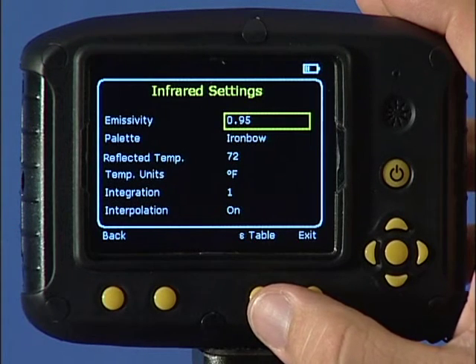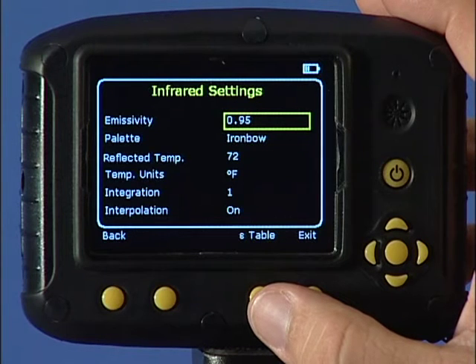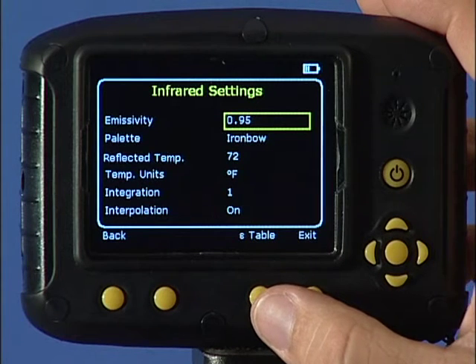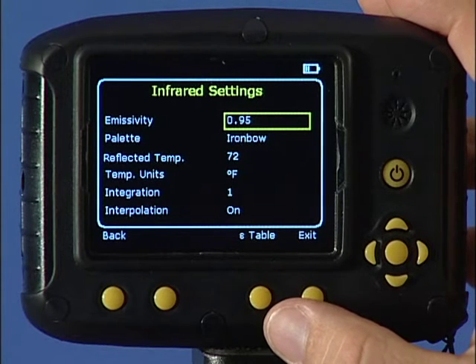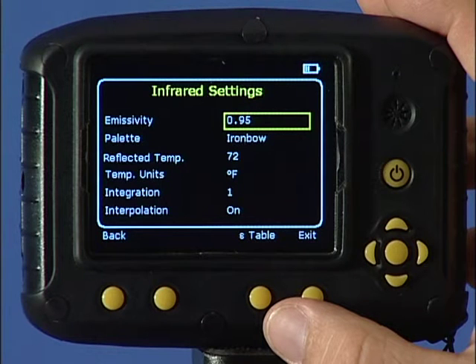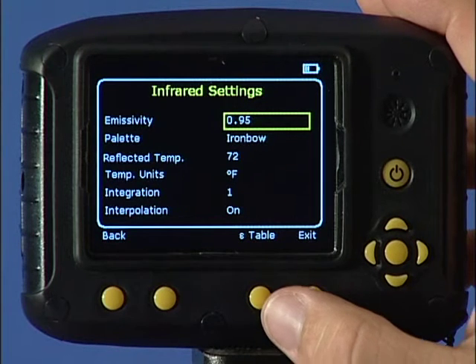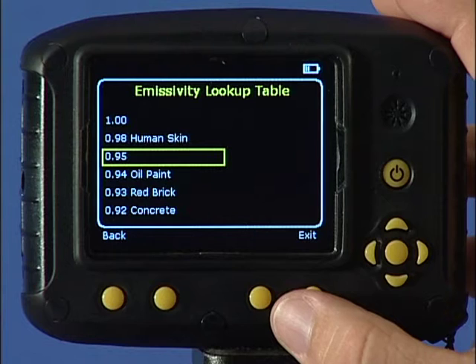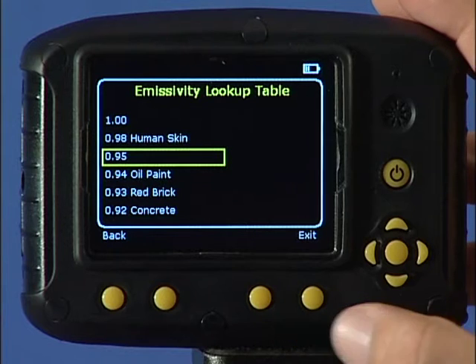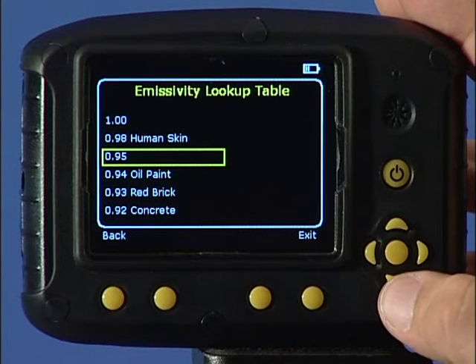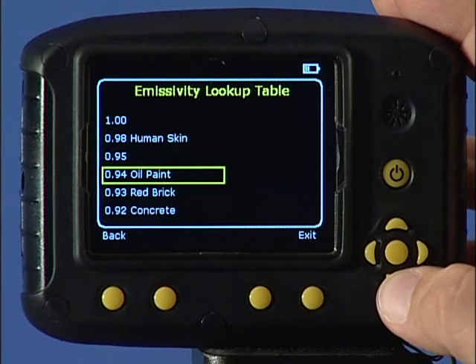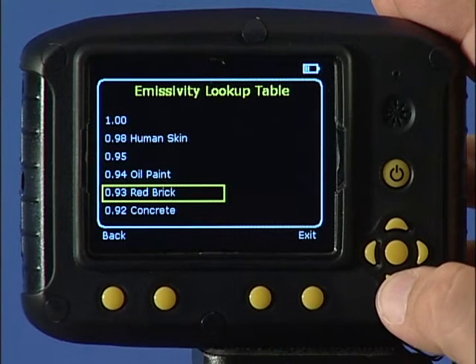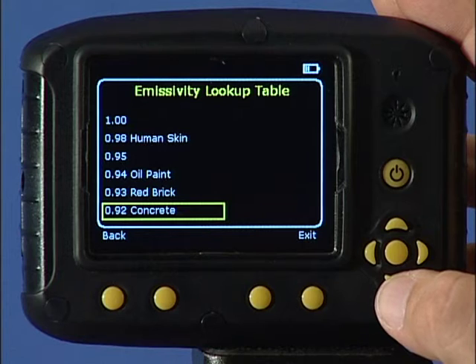Emissivity values can be changed to compensate for the reflective energy of a wide range of materials. For maximum accuracy, set emissivity by pressing function key 3 for a table of values. Then look up the material under inspection and make your selection using the up-down navigation keys.